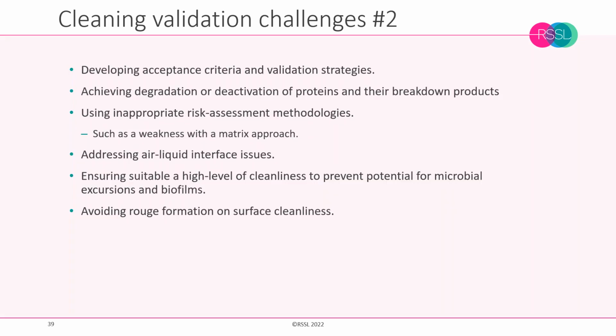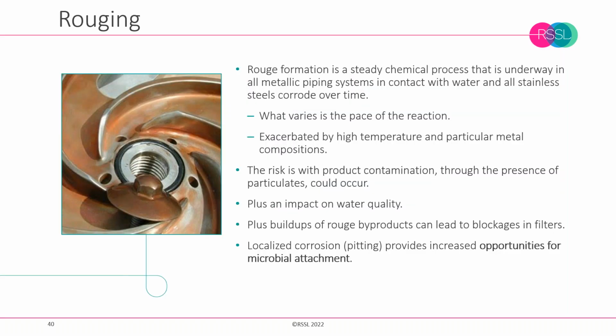Another concern is not developing appropriate acceptance criteria, failure to undertake risk assessments, and failure to assess things like air-liquid interfaces, or accounting for surface damage. And this can allow microbial deposits to build up. One of the biggest concerns here is rouging. There should be checks for rouging within equipment, and this can lead not only to the build-up of particulates, causing unexpected chemical reactions through the rouge product, it also causes corrosion and pitting, which leads to opportunities for microbial colonization.